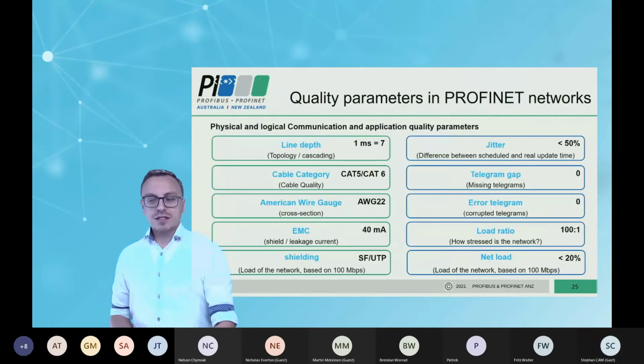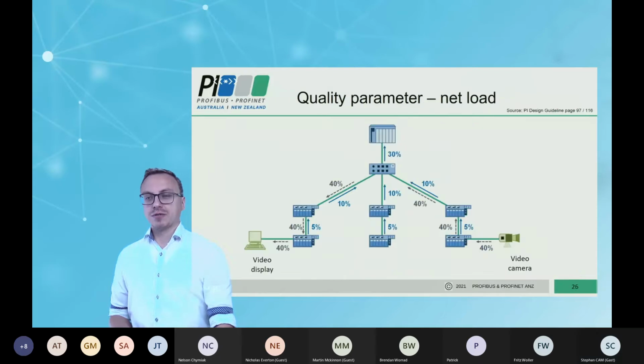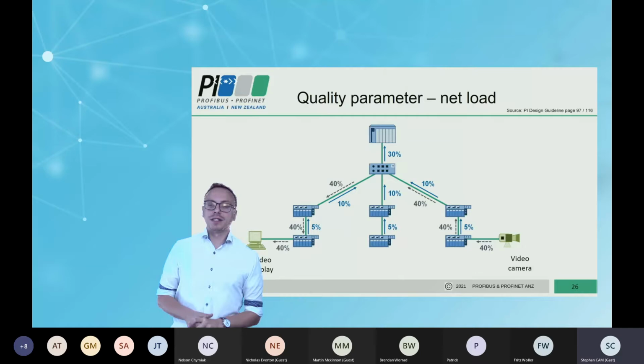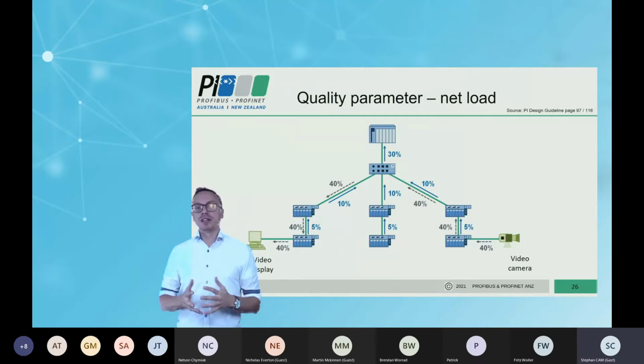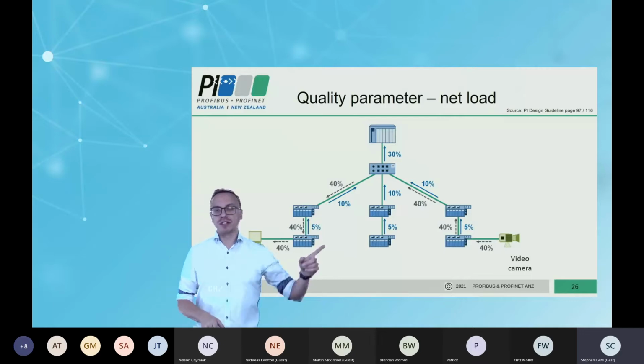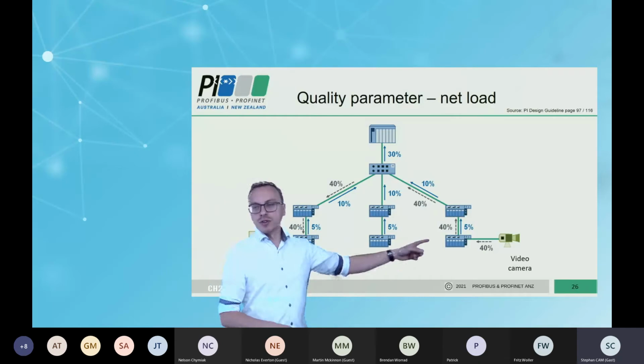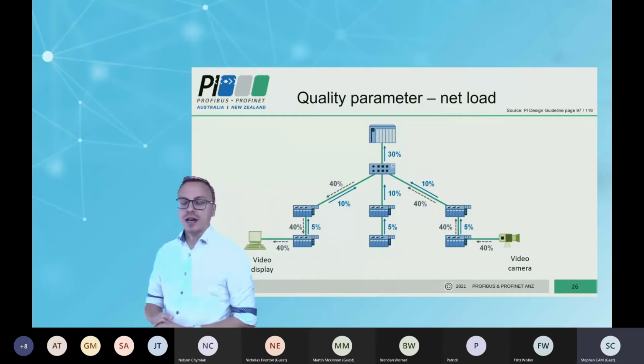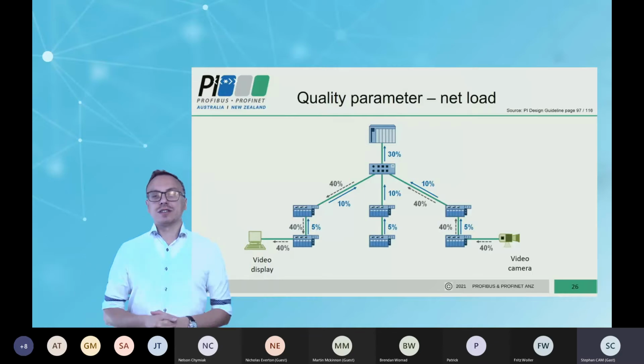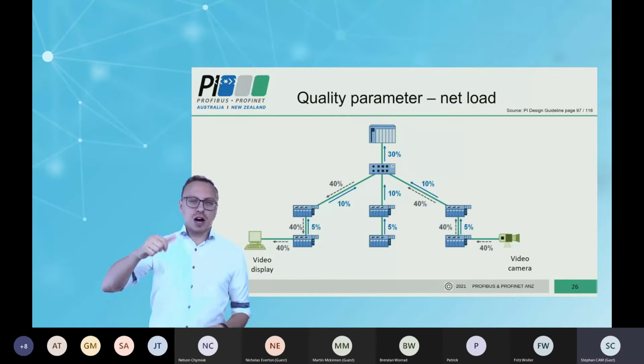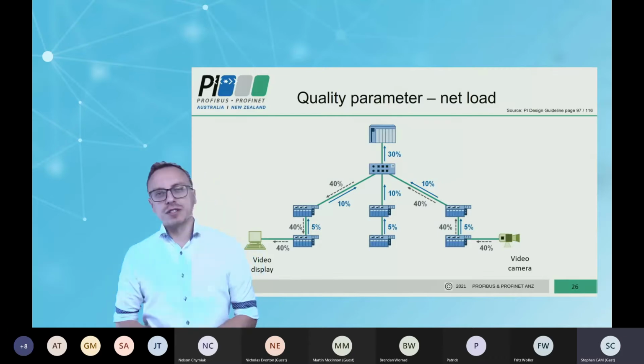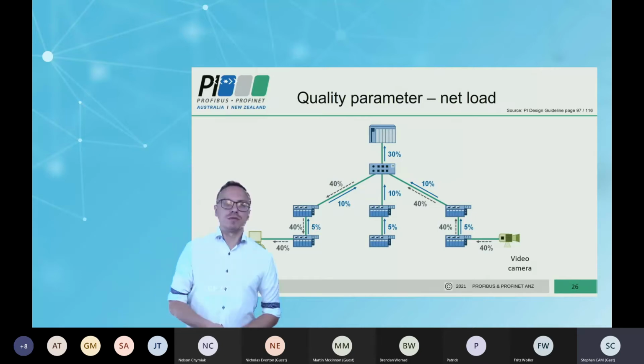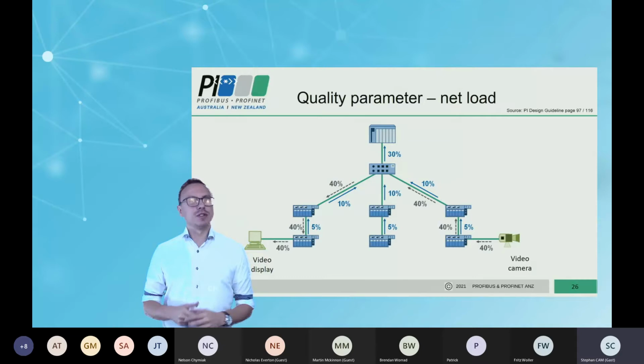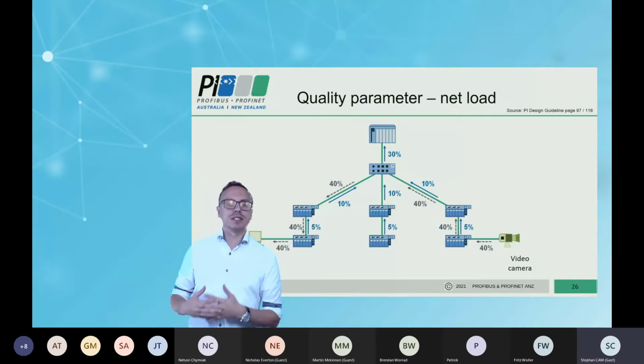So, and the last quality value is the net load. And here you see what could be the reason for net load. As I said, it could be your cyclical communication and it could be your non-cyclical communication, like this camera in this example. And all these devices will create net load. To get a feeling for how much net load one PROFINET node creates, you can say one PROFINET node with an update time of 1 millisecond will create around 0.6 up to 1% net load.